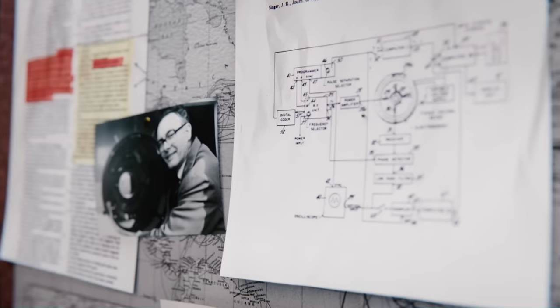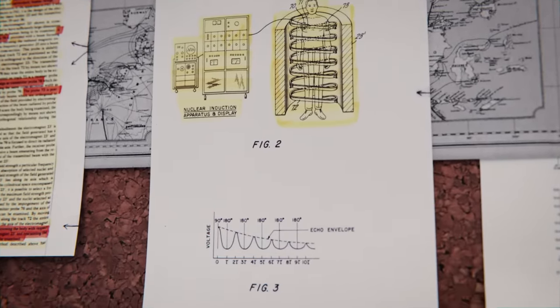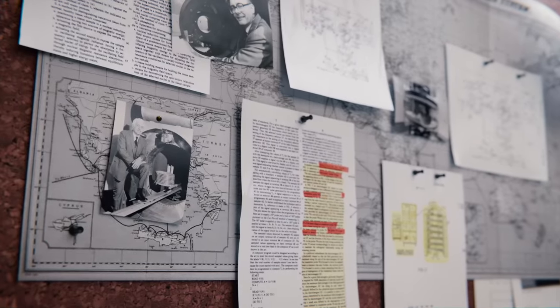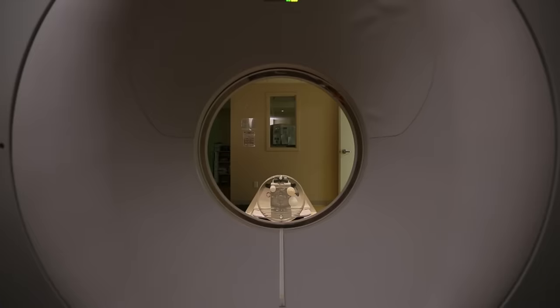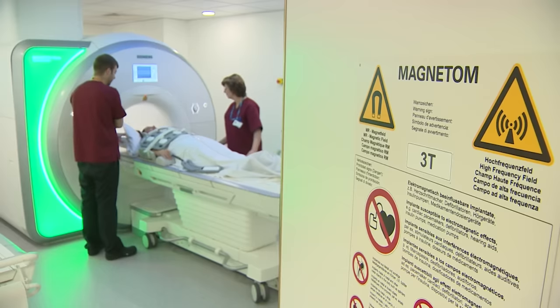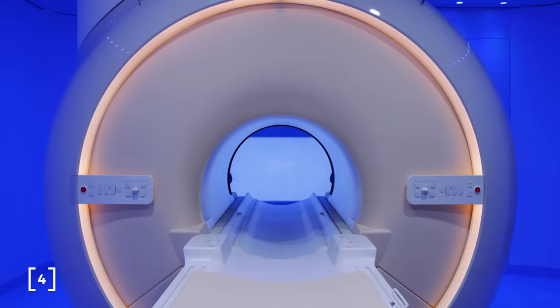Achieving this intense magnetic field comes as no easy feat. Early MRIs used permanent magnets as their source of the main magnetic field, but only reached strengths of 0.5 tesla, limiting the resolution of the machines. Electromagnets can be used to reach stronger magnetic fields, but standard electromagnets can't produce a 1.5 tesla field. Higher magnetic fields require higher electric currents that would melt ordinary wires. To achieve larger currents in the wires, engineers required superconducting coils.